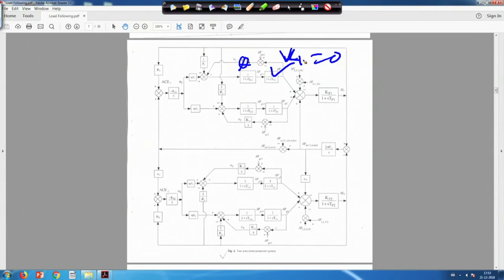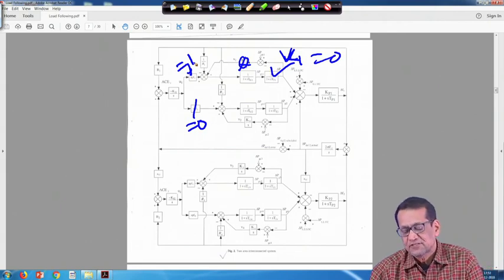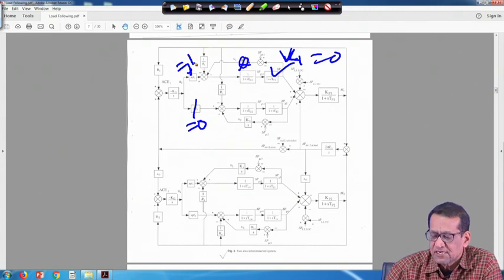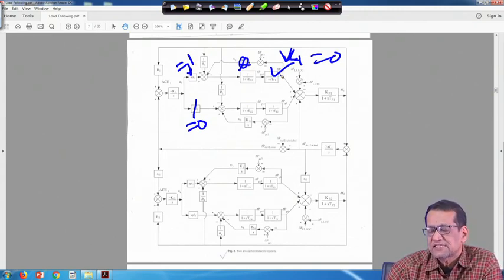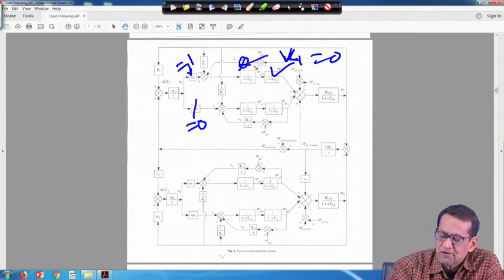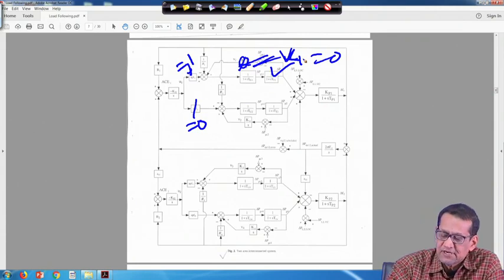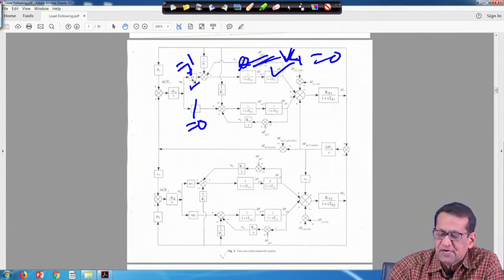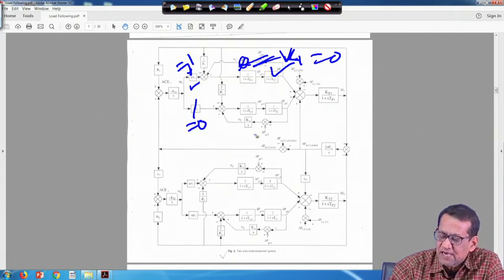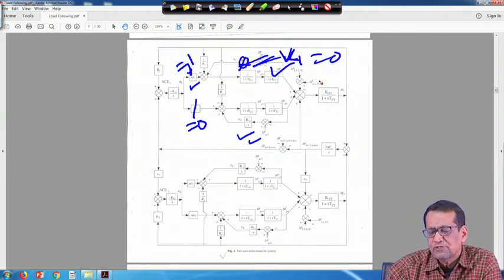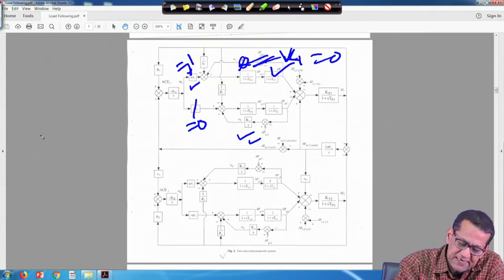Earlier when there was no uncontracted power demand, delta PG1 at steady state was 0. Now the load following controller is not there for unit 1 (k1=0), but it is under AGC because APF1 is 1. APF2 is 0 and unit 2 is under load following. There are two DISCOs in each area. Delta PL1 UC dash was 0.005 per unit megawatt demanded by DISCO 1, and delta PL2 UC is 0.